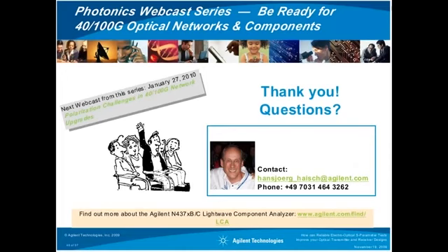The first question was from a participant who wanted to know if the instrument can measure laser performance parameters like RIN, relative intensity noise, or mode hopping, for example. Hansjoerg, can you say some words if we have these capabilities? Well, basically, yes. A network analyzer always has a calibrated receiver which can also operate like a spectrum analyzer.